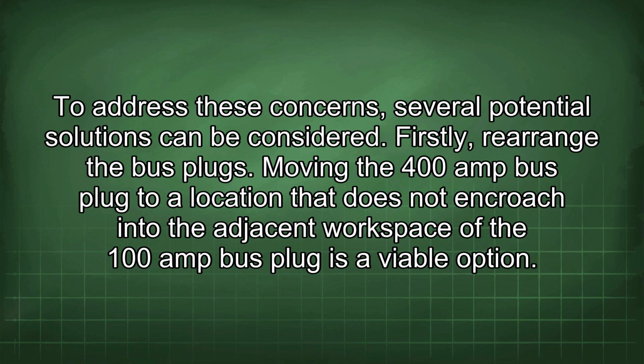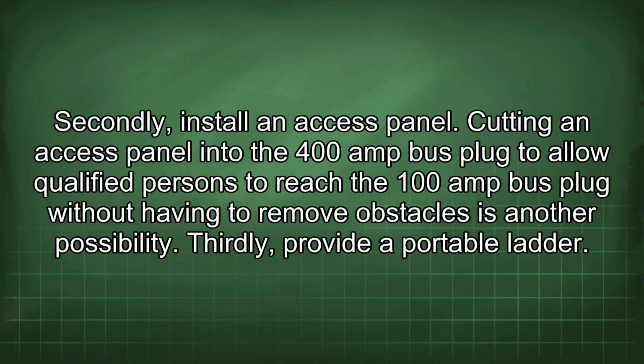Firstly, rearrange the bus plugs. Moving the 400 amp bus plug to a location that does not encroach into the adjacent workspace of the 100 amp bus plug is a viable option. Secondly, install an access panel. Cutting an access panel into the 400 amp bus plug to allow qualified persons to reach the 100 amp bus plug without having to remove obstacles is another possibility.